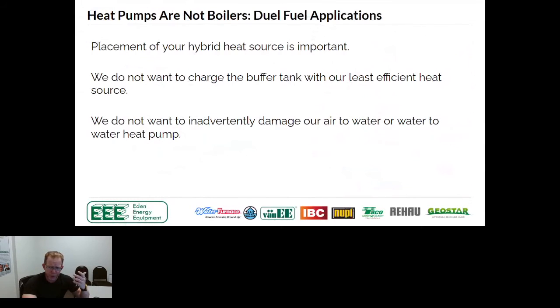As we move on, I want to talk a little bit about dual fuel application so everybody understands the importance of a dual fuel application. I'm pretty sure you're going to run into the scenario where you've sized your heat pump, you look at your design temperature, let's say it's 5 degrees Fahrenheit, you've got a 5-ton unit that doesn't quite get you to where you need to be. Now you need to figure out what your backup source is.